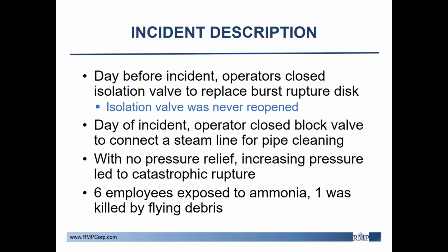On the day of the incident, another operator closed the block valve that isolated the ammonia pressure control valve from the heat exchanger. He proceeded to connect a steam line to the process for cleaning. However, since the block valve and the isolation valve were now both closed, the flow of steam had nowhere to escape. Pressure could not be safely vented, and the heat exchanger ultimately ruptured. Flying debris killed one employee walking nearby instantly, and 6 others were exposed to the ammonia release. The plant was evacuated. Unfortunately, the employee tracking system also failed to account for all workers, so everyone assumed the plant had been fully evacuated. The body of the killed employee was not found until several hours after the plant operations had resumed.